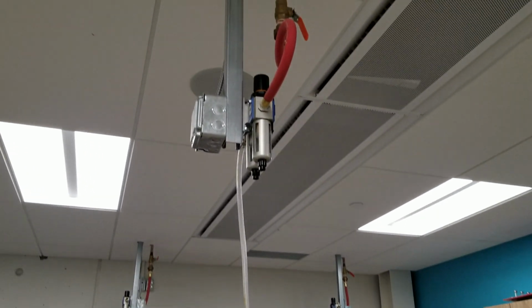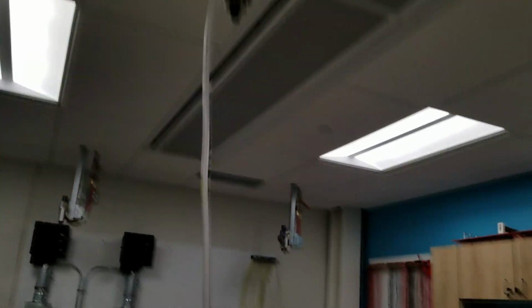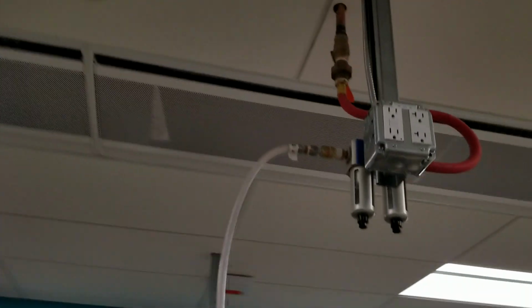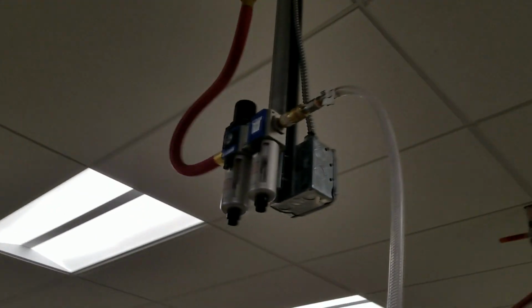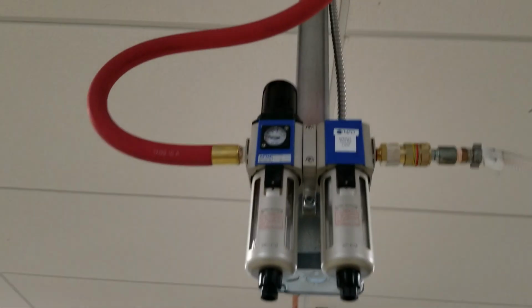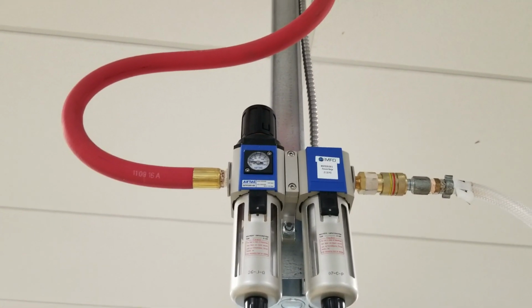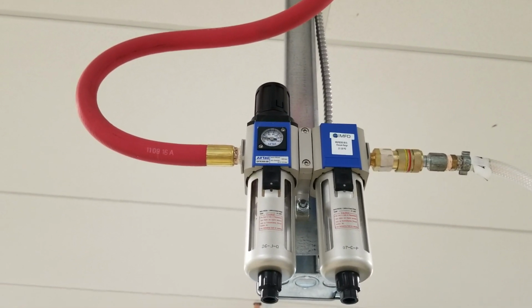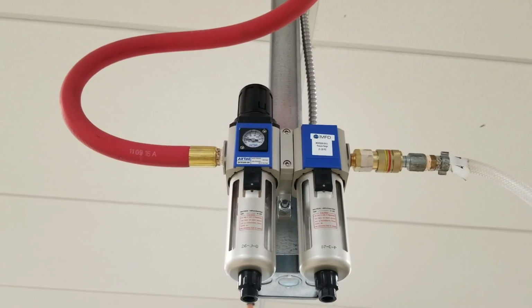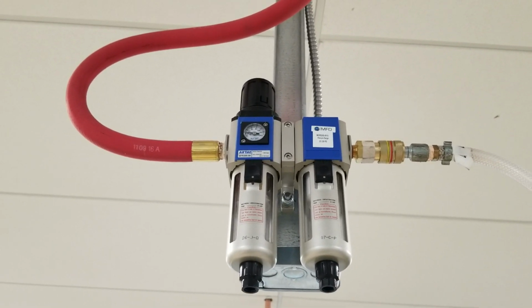Pressure transducer calibration. Connecting our air lines, making sure our regulators are properly adjusted. This is our regulator. Just remember, if you turn a regulator clockwise, which would usually be tightening something down, your pressure will increase on your regulator.